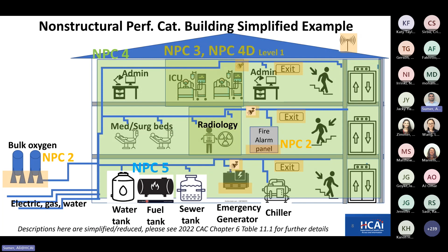On the other hand, NPC4D, starting with level 1, looks at these spaces and asks the question, what is the operational plan of this building, by looking at what is not braced and what alternative ways there are to provide these services. NPC4 is a more holistic approach, so it looks at everywhere in the building and braces equipment and the distribution system. There is no operational plan attached to NPC4 because the assumption is the building will be code compliant. NPC5 is only given when the building is either NPC4D or 4, and the water tank, fuel tank, and sewer tank are evaluated for 72-hour operation. So that's, in a nutshell, all of the ratings.